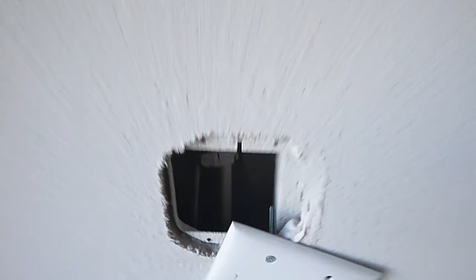This is the UFR - this is the main ground for the house. Main ground is labeled inside of the panel like it should be. Neutral is labeled inside the panel like it should be. You have the plastic protection booties for L1 and L2 like you should. This basically is a textbook installation.